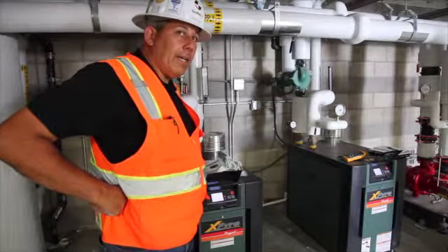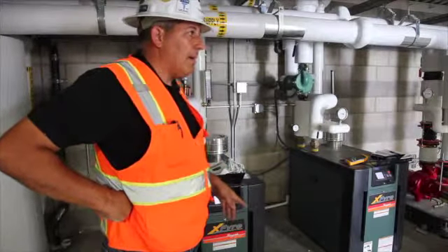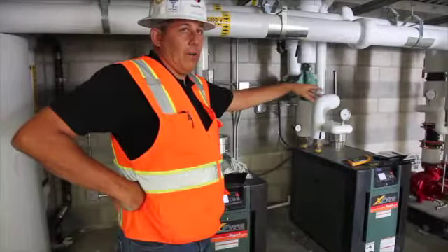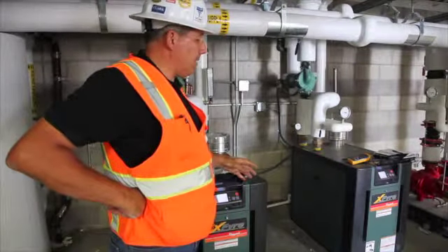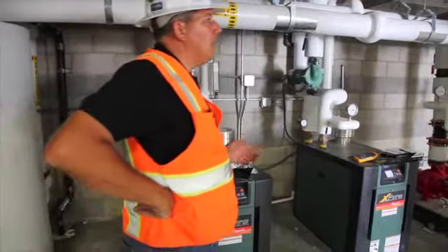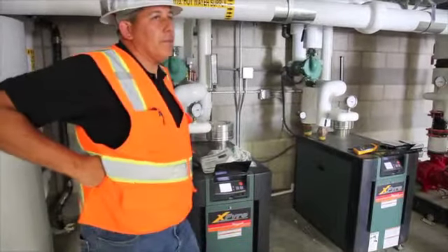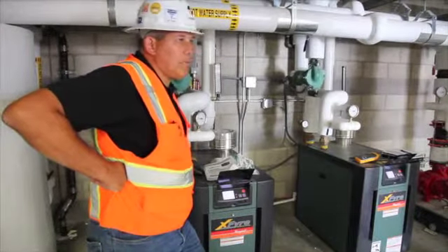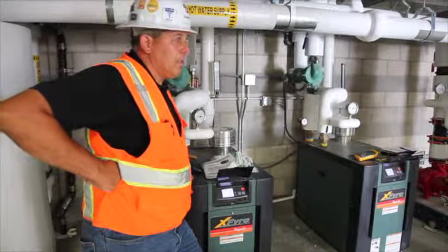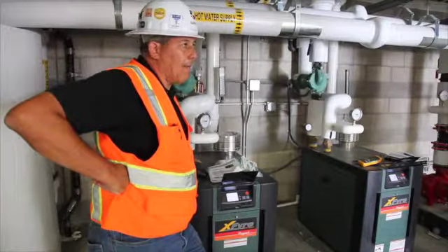However, being this is the lead, it looks at runtime, and it can run either boiler to maintain runtime. But the enable signal comes from the BMS. So it gives it a dry contact closure to start them. And what I mean by starting is, it tells it, okay, you can start if the temperature is too low. And then the automation also sends a different voltage signal, from 2 to 10 volts DC, to go from a set point of 120 to 140. So that set point is going to vary based on outside air temperatures.